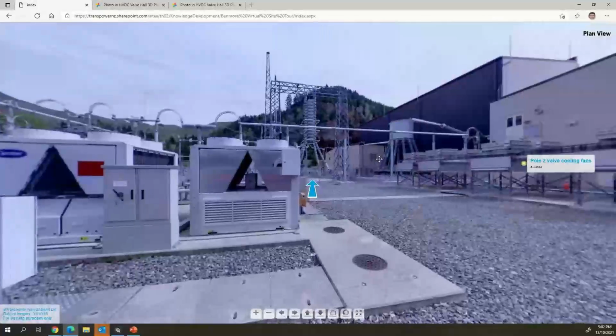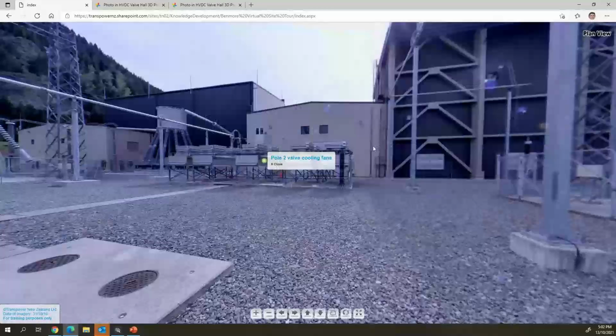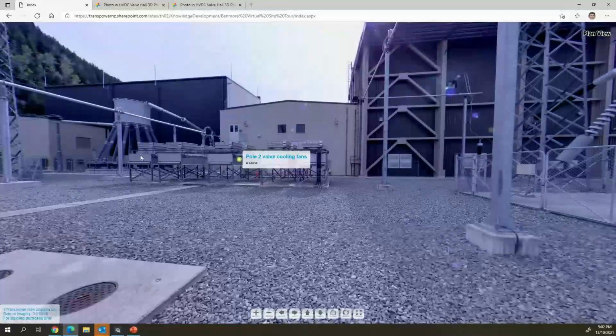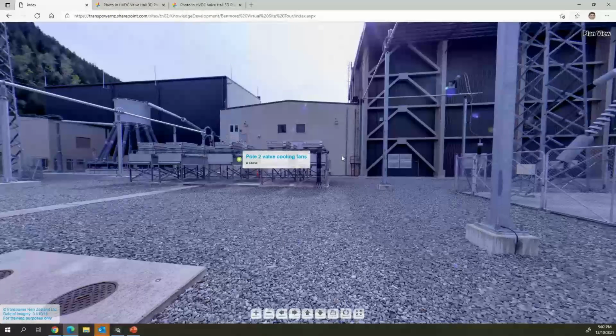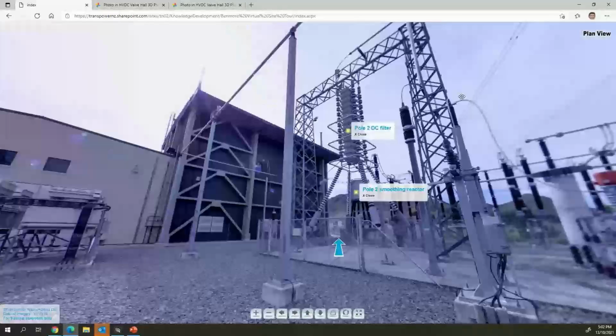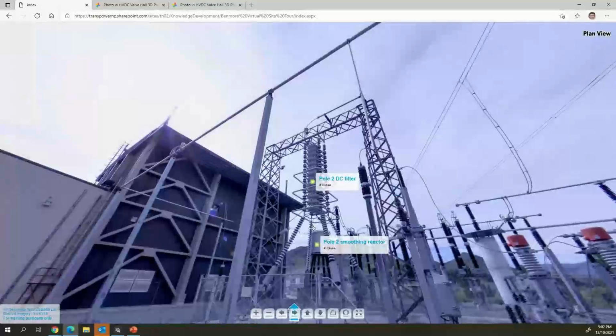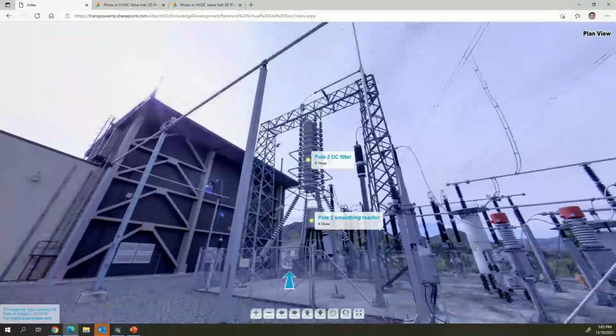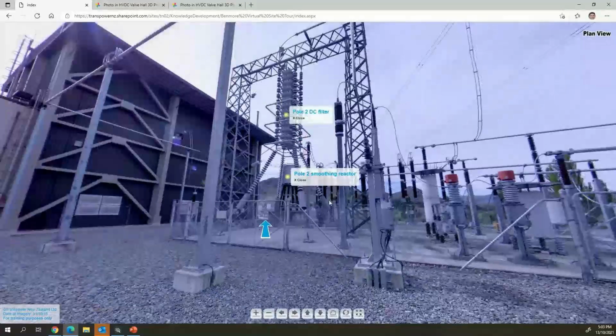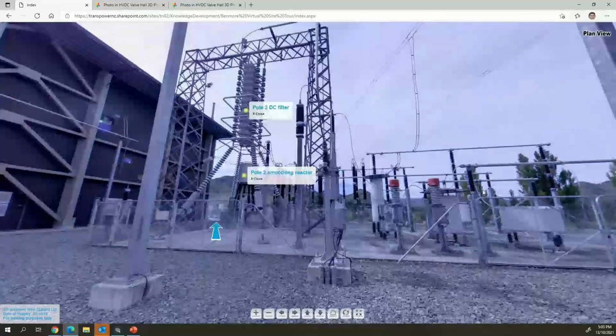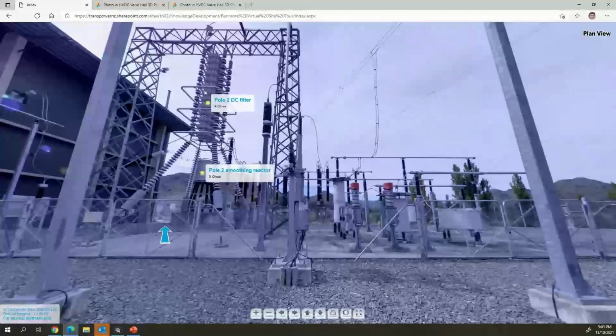Here's the pole 2 reactor there. Here's the cooling. This is the cooling fans for the valve cooling. There it comes outside. This is the DC filter here. So that's the capacitor bank for the DC filter. And we've got all these other components here like reactors and resistors. But again, as I said, if we had a failure in here, we can actually switch it out and continue running.